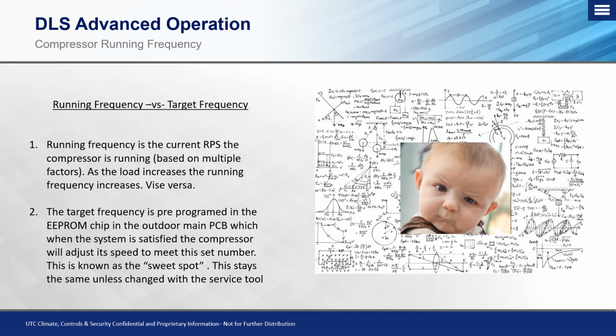So when we look at that as the system is being satisfied, the compressor will adjust its speed to meet this set number. We often refer to this as the sweet spot of the system. Okay, so if we have, let's just say, a system that's starting up and we have 4 indoor units that are calling, they're all roughly about 4 to 5 degrees away from set point.